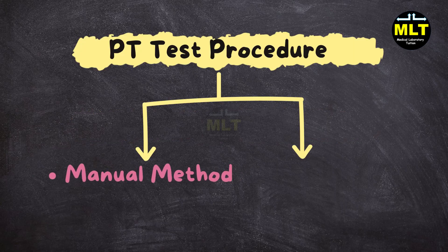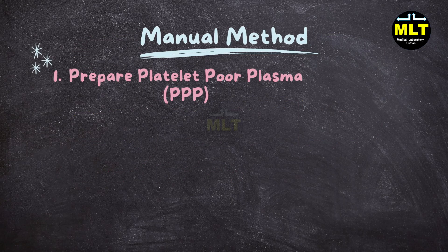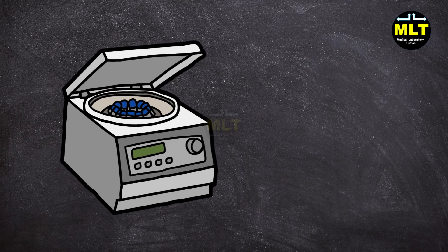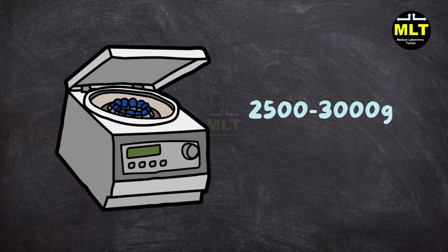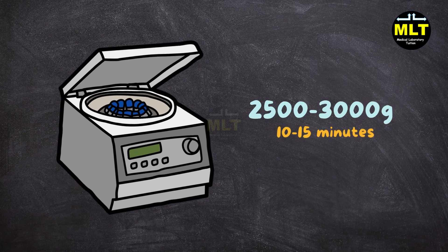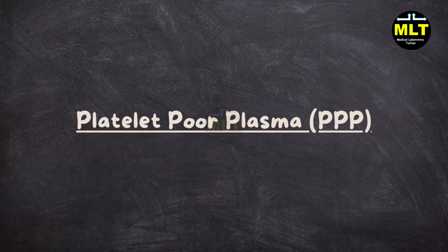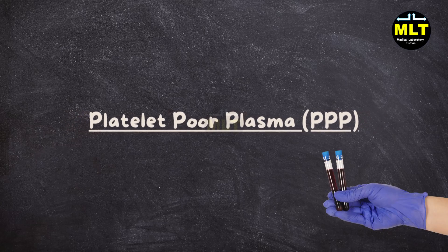Step-by-step PT test procedure — manual method. Step 1: Prepare platelet-poor plasma (PPP). Centrifuge the blood sample at 2500–3000 G for 10–15 minutes to obtain PPP. This is the base of our PT test.